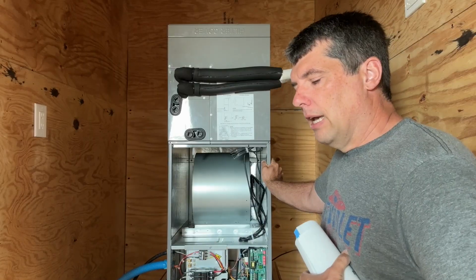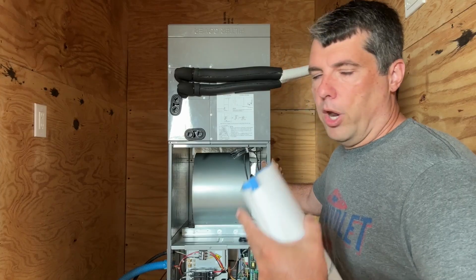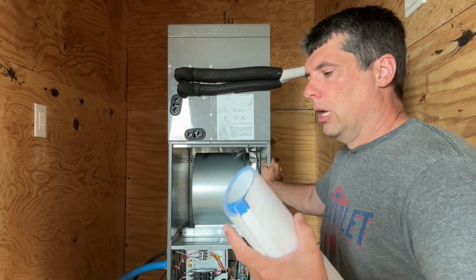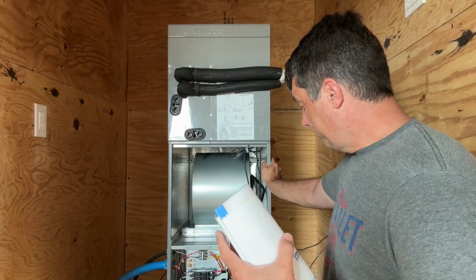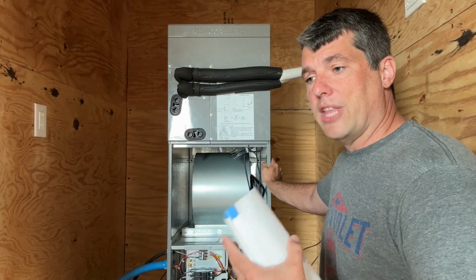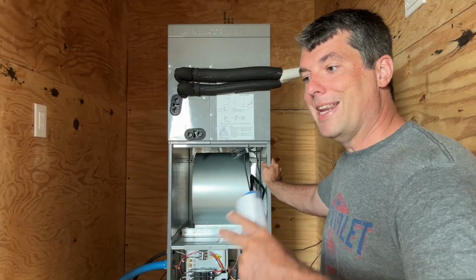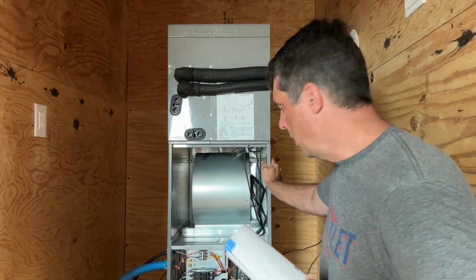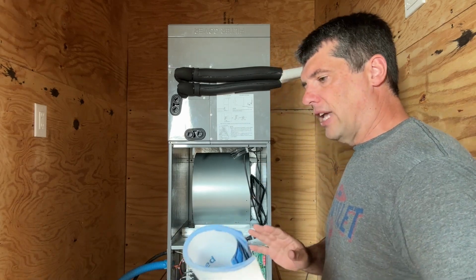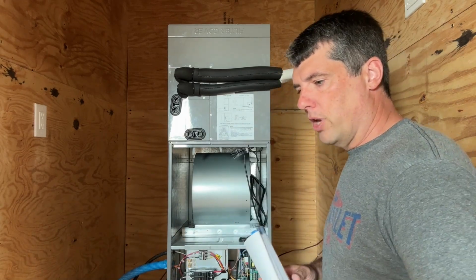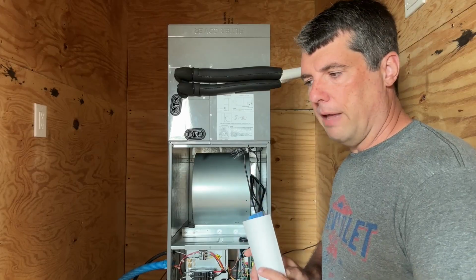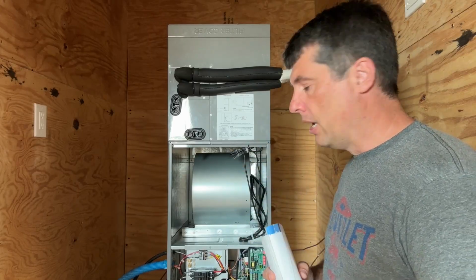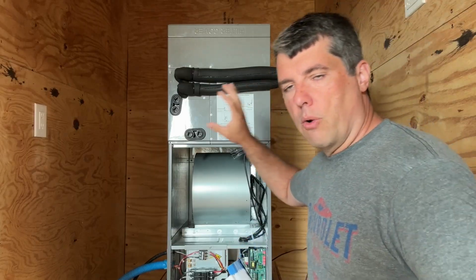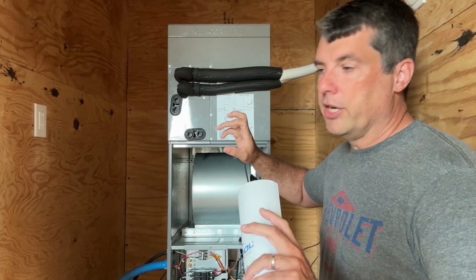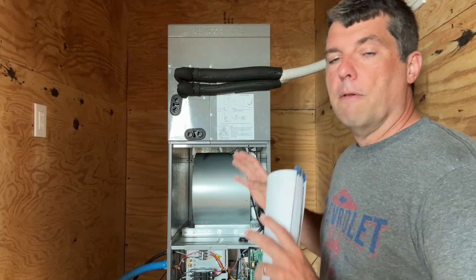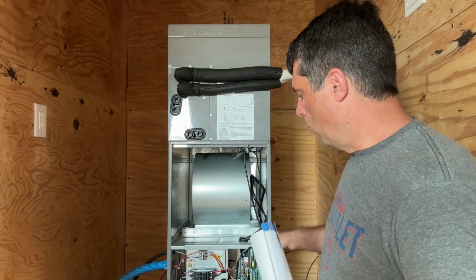So in that case, if you look at your thermostat wiring, you're going to have a Y1 and a Y2 if you have a two-stage unit, which I do. The reversing valve is going to use that same Y1, Y2 for both heating and cooling, depending on the position that the valve is in. This is a single transformer unit. You have one 24-volt power supply that's running to the thermostat. Without power to this unit, you don't have power to the thermostat, kind of, because the Nest has a backup battery that will power the thermostat for a little while once you lose power to this unit.